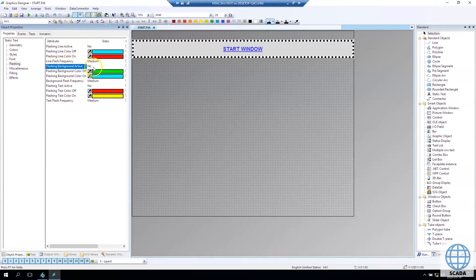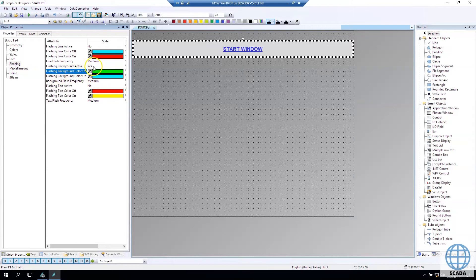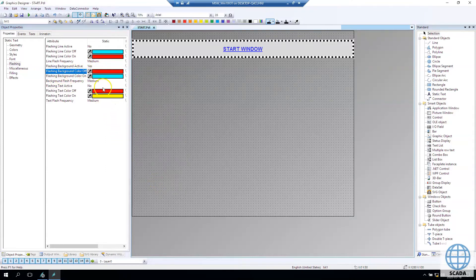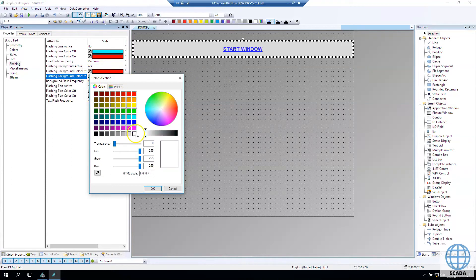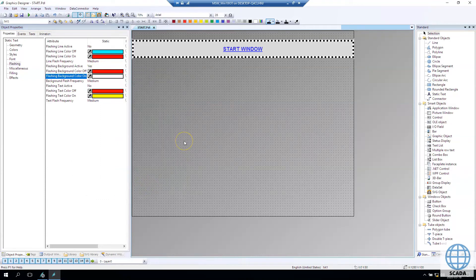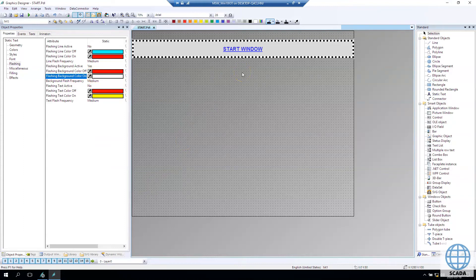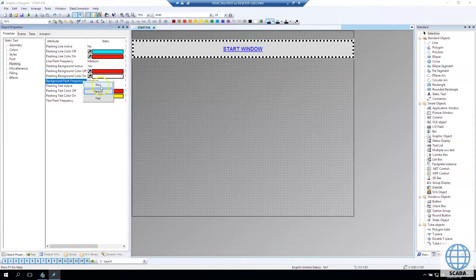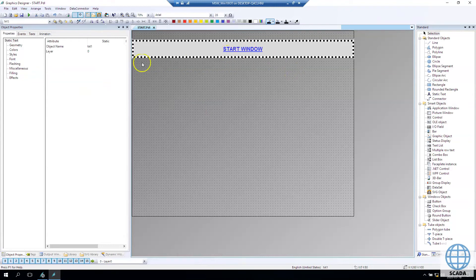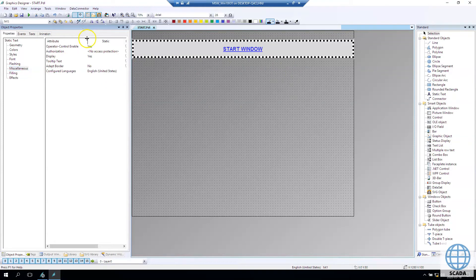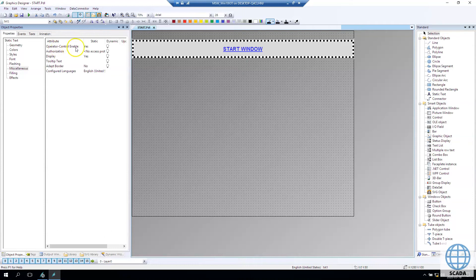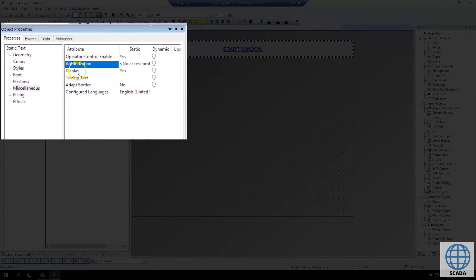We need to make some flashing on our screens so operators know that this element has some problem. So if you make good flashing inside your application for the core elements you can make the operator understand better what's wrong with your system, with the industrial system. In miscellaneous tab you have information about authorization level or if operator or technician can operate with our elements. If operator control enable is no so no one can click on this during runtime.